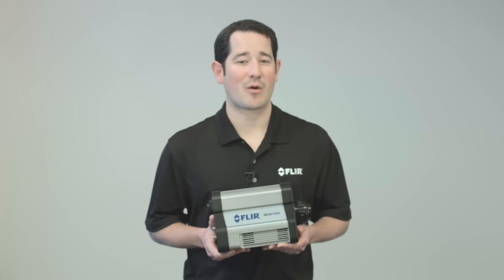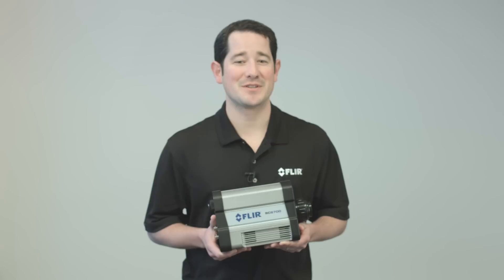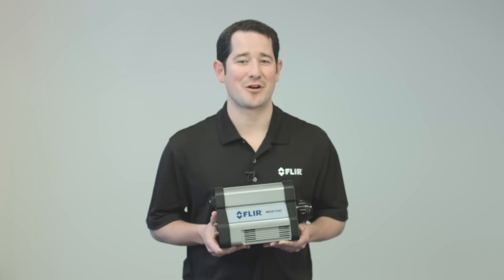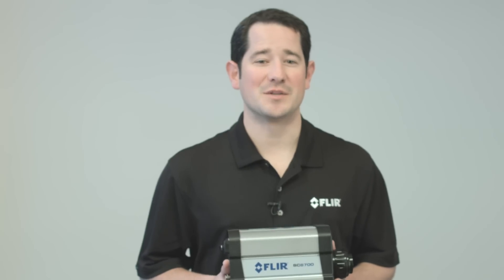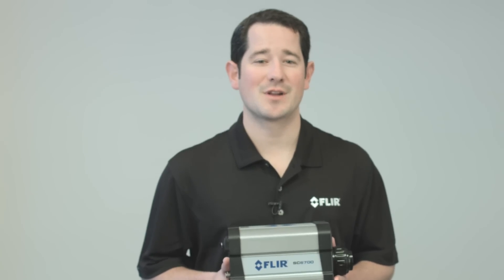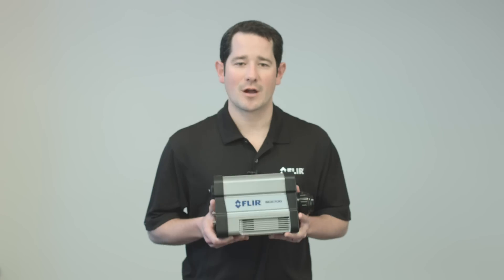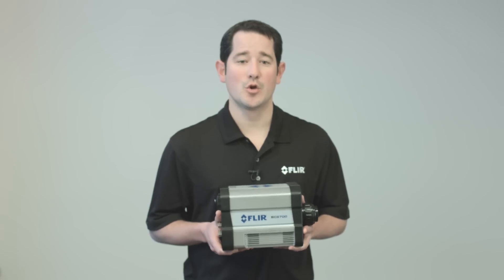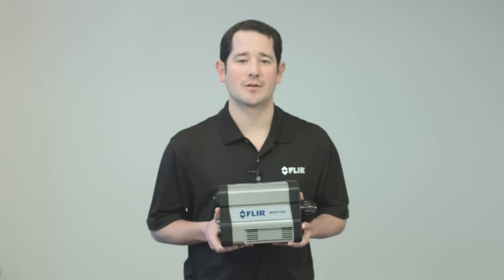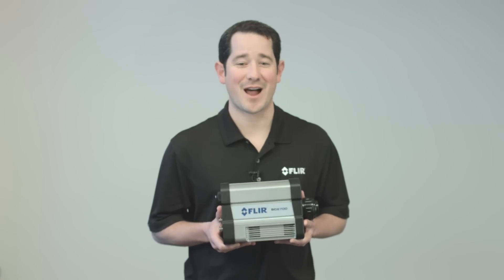However, even if your thermal application does not require a specific wave band, there can still be some surprisingly compelling reasons to consider the SC6700 Long Wave IR Camera. Specifically, SLS technology boasts ultra-short integration times along with a high dynamic range. Therefore, when we calibrate the SC6700 camera to measure temperature, you can realize broad temperature ranges and stop motion on fast-moving targets at the same time.